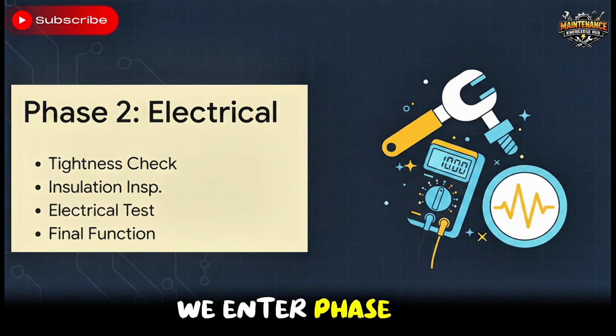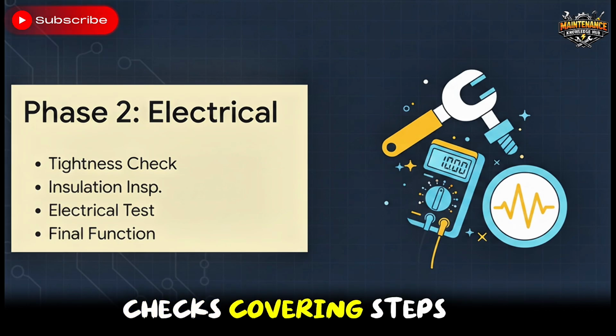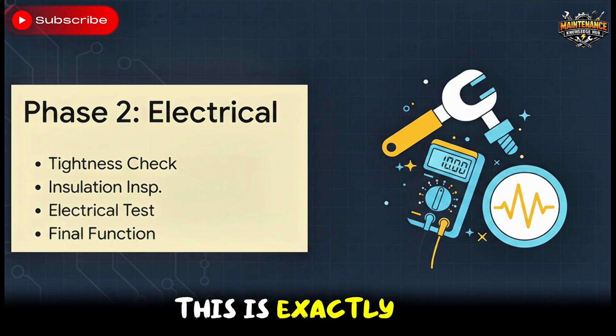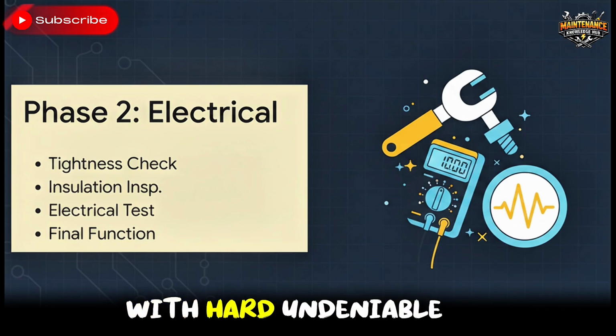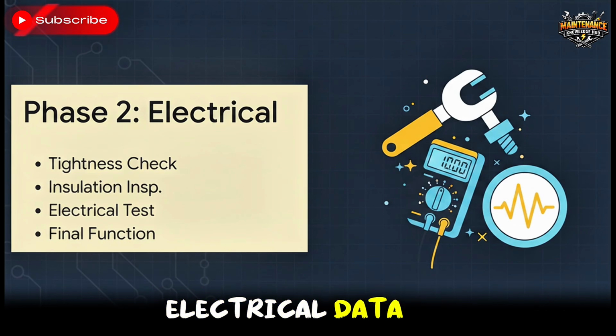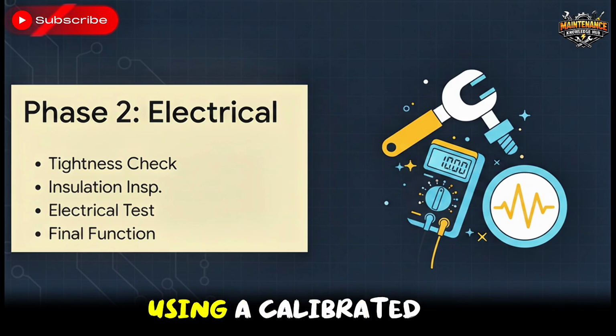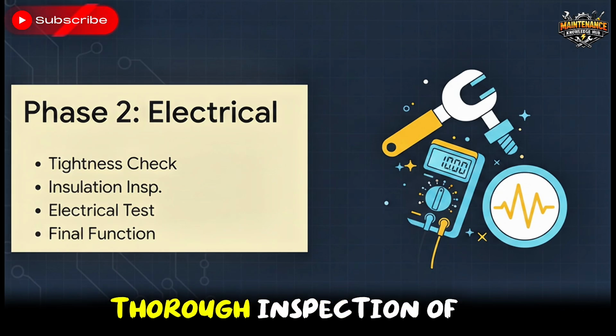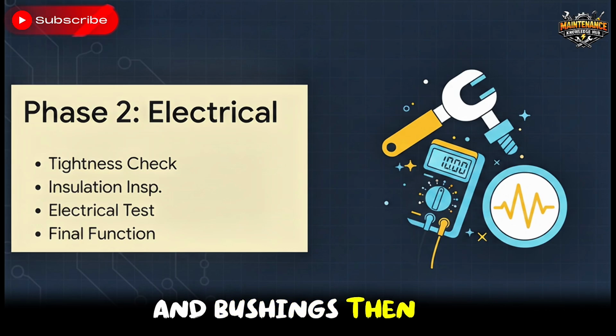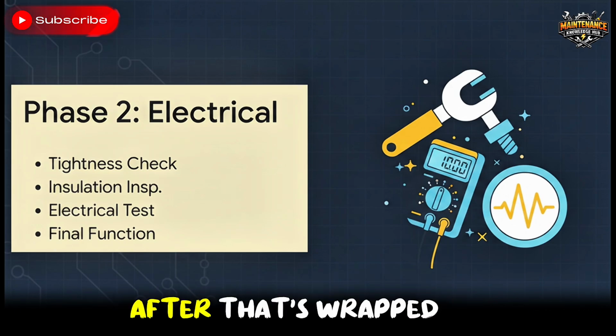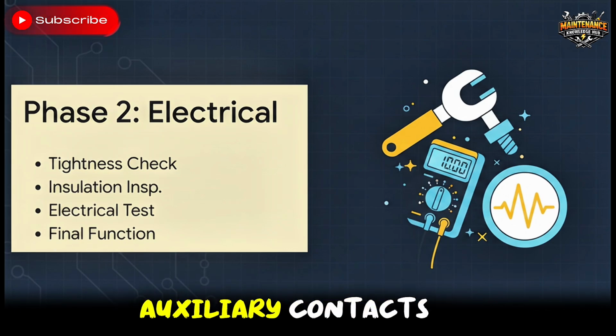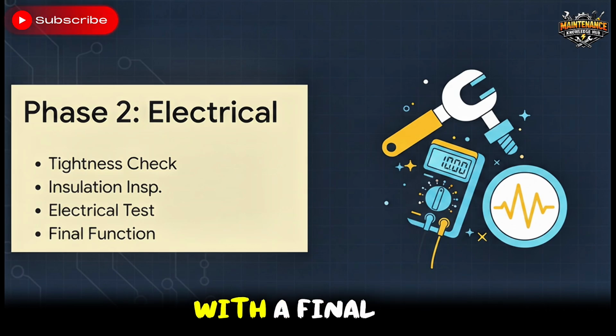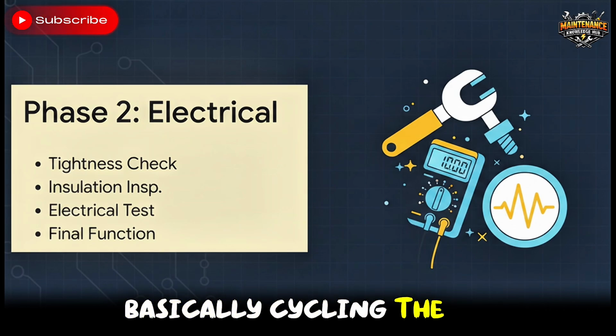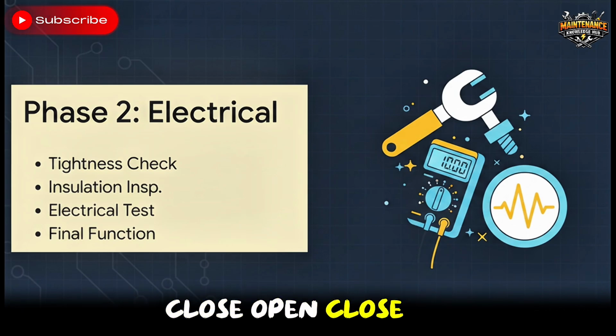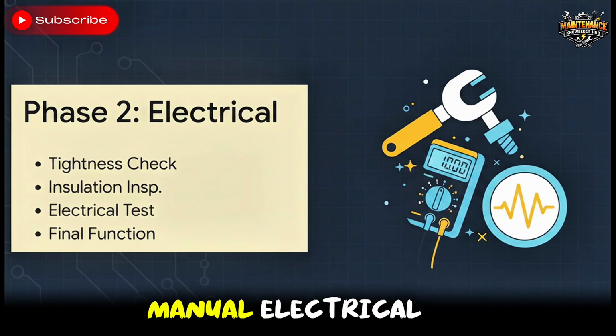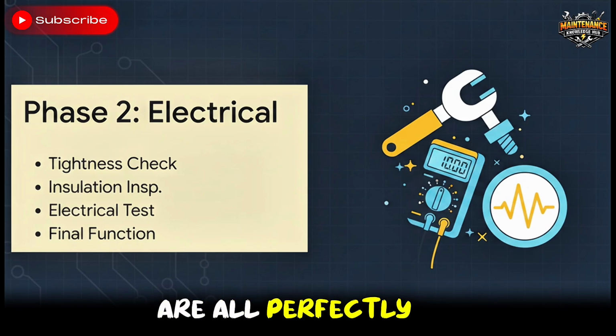Moving right along, we enter phase 2, electrical and final checks, covering steps 7 through 12. This is exactly where we confirm all of our mechanical work with hard, undeniable electrical data. We begin with a tightness check of all terminals using a calibrated torque wrench, followed by a thorough inspection of the insulators and bushings. Then we get into our electrical testing. After that's wrapped up, we inspect the charging motor and auxiliary contacts. And we bring it all home with a final functional test, basically cycling the breaker through several complete close, open, close operations. This ensures the manual, electrical, and control circuits are all perfectly aligned.